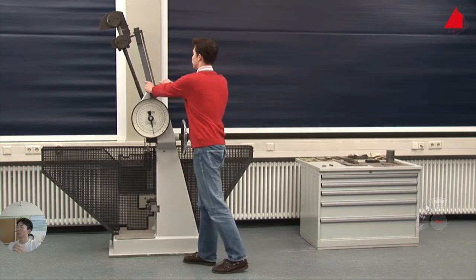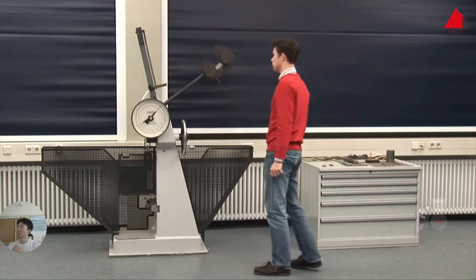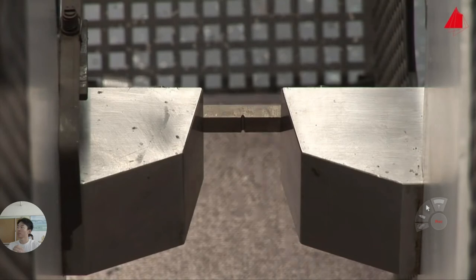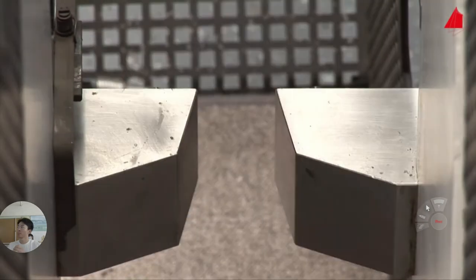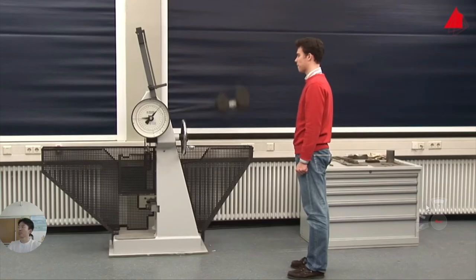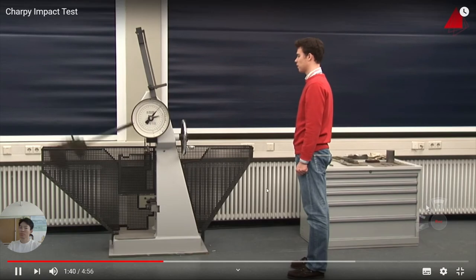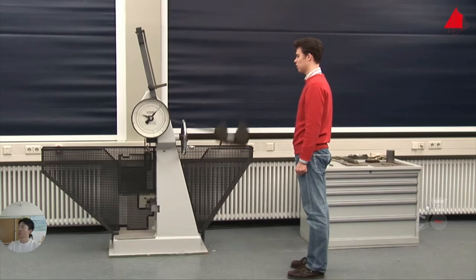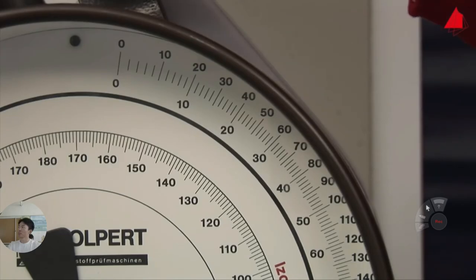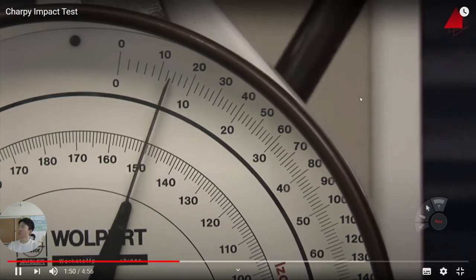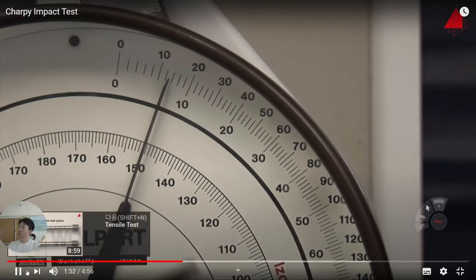Perfect, the test can begin. The pendulum is released, it swings downwards and hits the specimen with its rounded hammer peen. The specimen absorbs part of the pendulum's energy, so the pendulum doesn't reach the full height on the other side. The amount of energy that has been absorbed by the specimen can now be read off at the position of the drag indicator. It only amounts to 13 joules in this test.